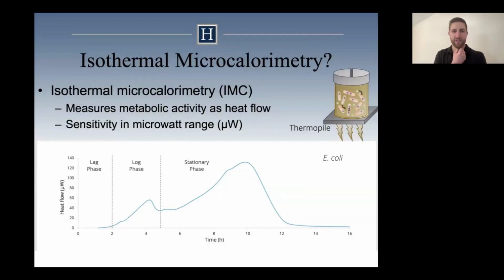So why calorimetry? We thought isothermal microcalorimetry would be a potentially interesting technique to investigate in this space. The reason behind that, and the technical workflow for that, is that calorimetry measures metabolic activity as heat flow. So the theory behind it is if bacteria are alive and metabolizing, growing or not growing, as long as they're metabolizing, they're producing heat, and we can detect that if the sensors are powerful enough to do so. So we figure that would have a nice potential improvement on time, given the increased sensitivity, where they don't actually have to be growing.